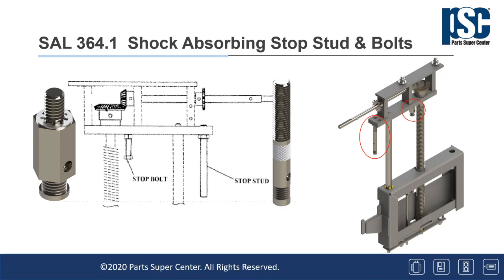The purpose of the existing stop studs and bolts is to protect against over travel if the upper mercury limit switch either fails or is out of adjustment. The stops prevent damage to the primary disconnects and elevating mechanisms by mechanically impeding any further travel of the breaker in the upward direction once the breaker lifting rails hit the front stop stud or the elevating mechanism lifting box hits the rear stop bolt.